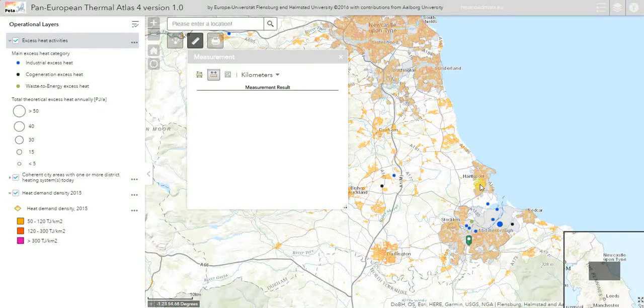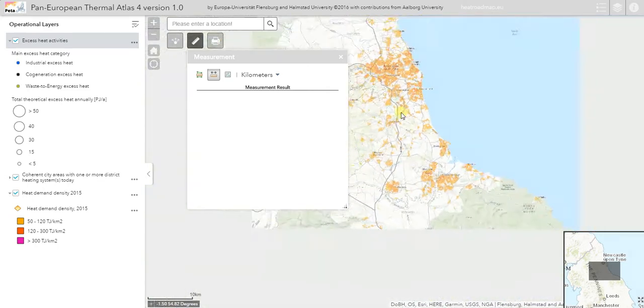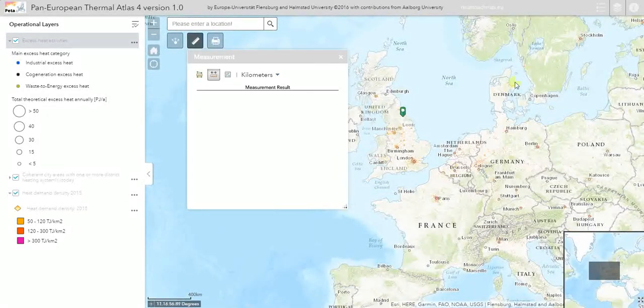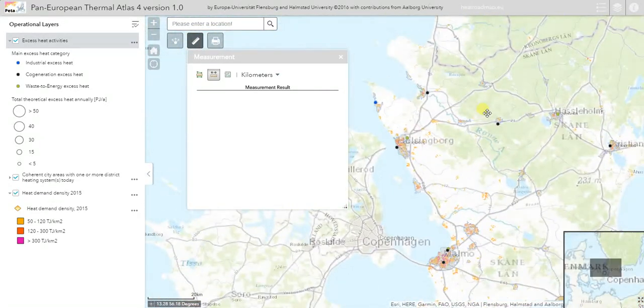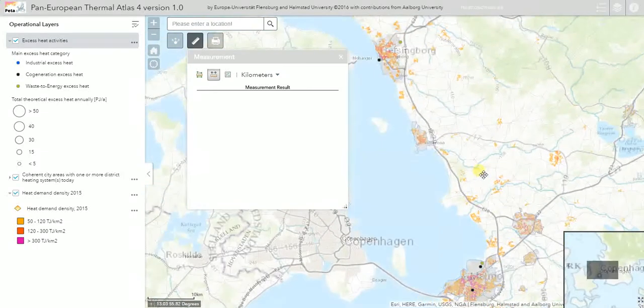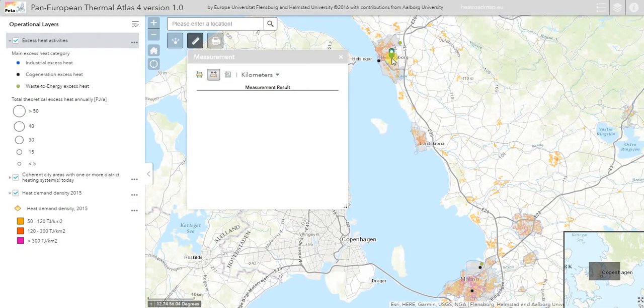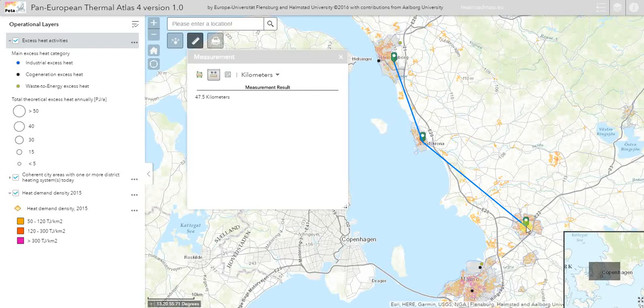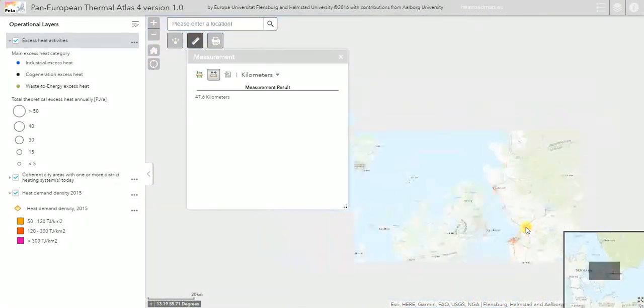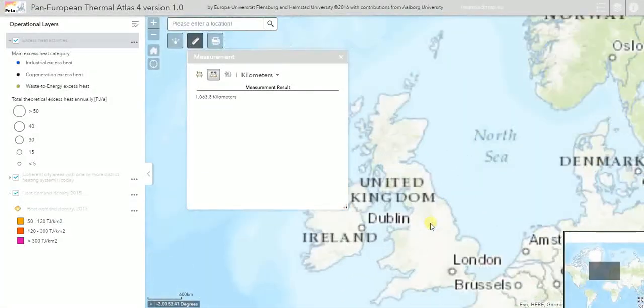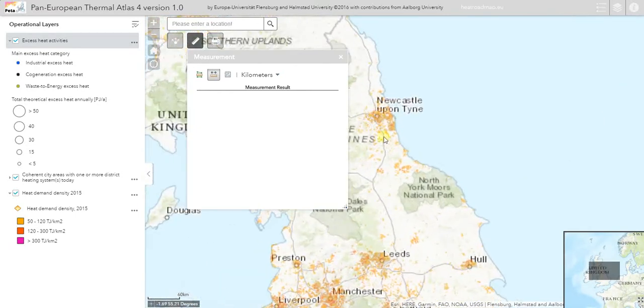Outside Middlesbrough there is substantial heat demand in Hartlepool, and a huge heat demand in Newcastle. Looking at Sweden as an existing example — a country with extensive district heating developed over the last 40 to 50 years — the cities of Helsingborg, Landskrona, and Lund started as independent district heating networks but are all connected today. The distance from north to south across those cities is approximately 50 kilometers, which we can use as a guideline for developing a long-term strategy for the Middlesbrough region.